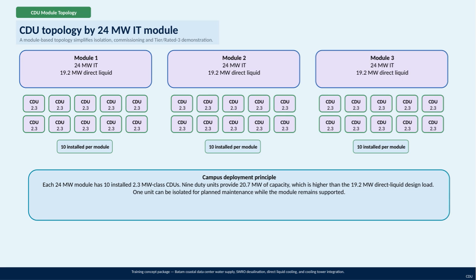Within each module, there are 10 CDU units installed, each rated at 2.3 megawatts. Importantly, out of these 10 CDUs, 9 act as duty units providing a combined capacity of 20.7 megawatts, which exceeds a direct liquid cooling design load of 19.2 megawatts. This configuration ensures there is always reserve capacity. That means one CDU can be taken offline for planned maintenance at any time without impacting the overall cooling support for the module. This modular and redundant setup not only increases operational flexibility, but also enhances system reliability, enabling continuous cooling performance critical for high-density data center operations.